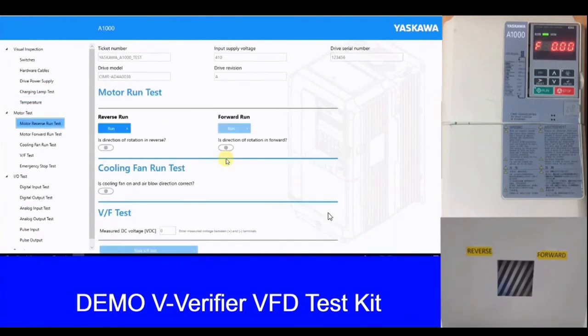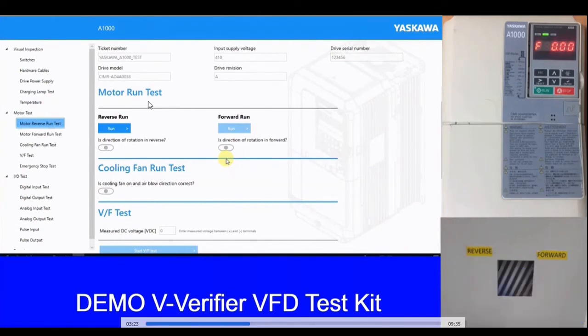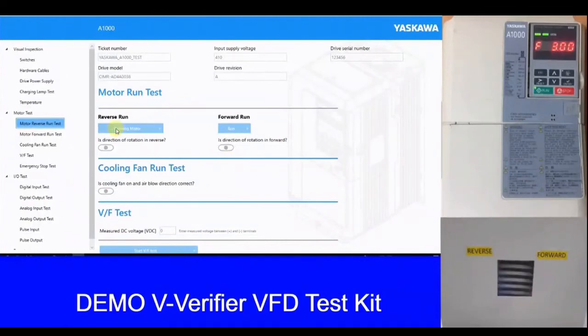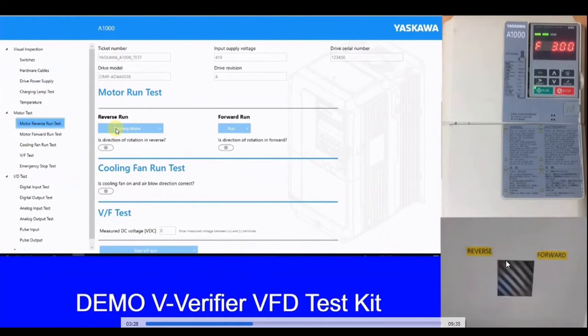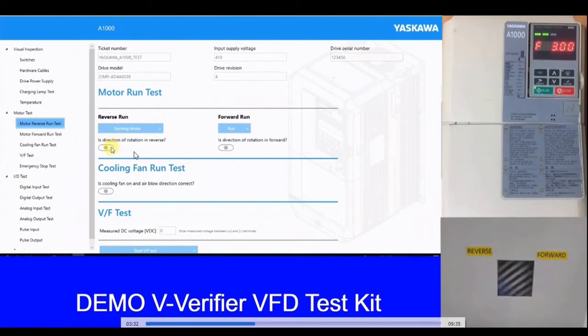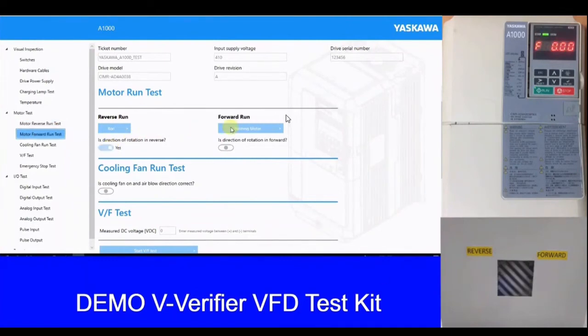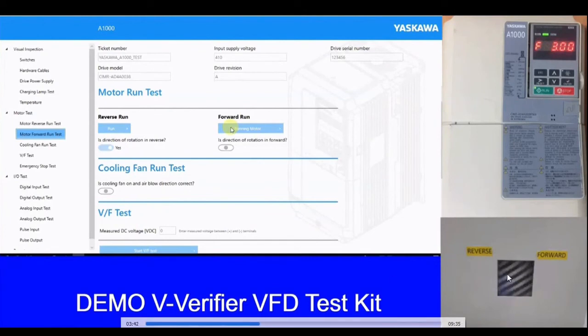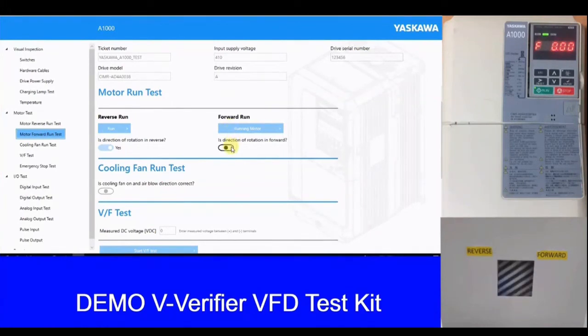Next we go to the motor test. In the motor test, we have reverse run and forward run. When you press the run button, the motor starts rotating in reverse, and this will run for 10 seconds at a frequency reference of 3 Hz as shown on the display. After 10 seconds, we verify that the direction of rotation is correct — that it is in reverse. We then proceed with the forward run, where the motor runs in the forward direction for 10 seconds at 3 Hz, to verify that both forward and reverse direction of the motor are properly working.